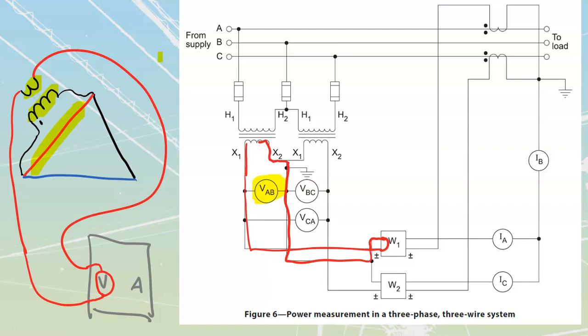Taking a look at my CTs, I see that my CT is connected—the primary of the CT goes in line with my actual lines going out to the load there. So I'll go from here and follow this down, through the ammeter section of the watt meter, then through another external ammeter, then back up from this external ammeter through another meter—we'll talk about that in a minute—all the way back up to my load itself.